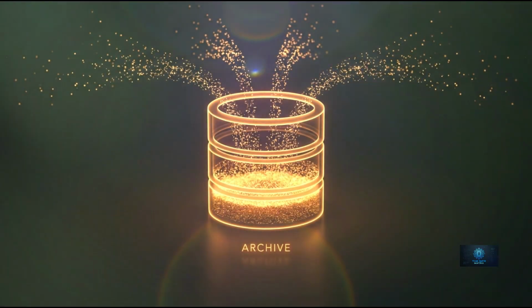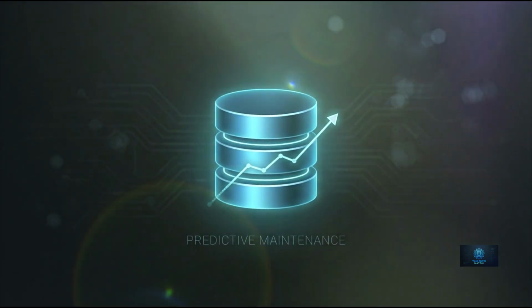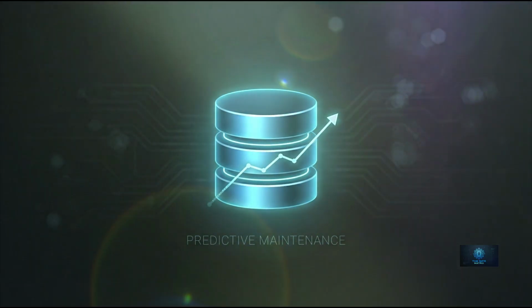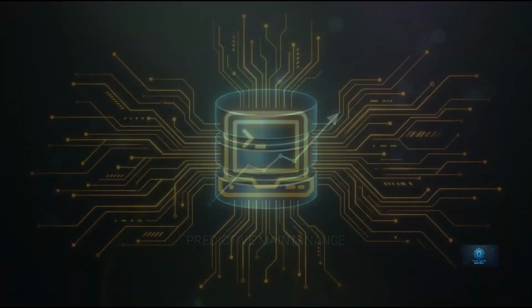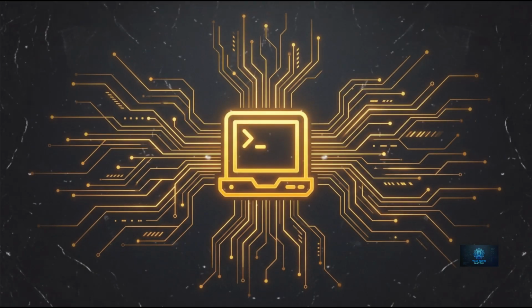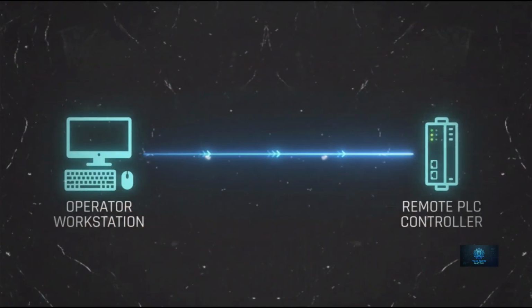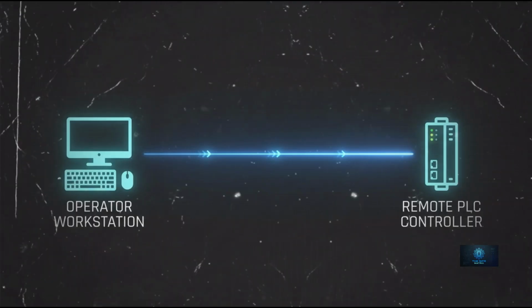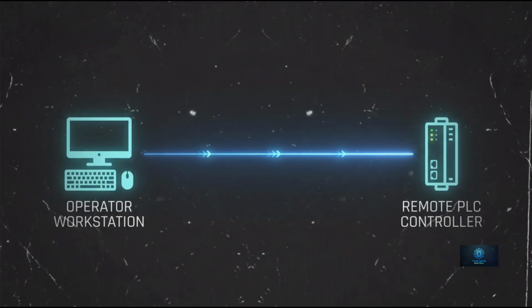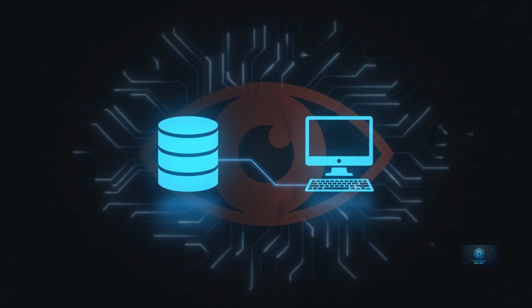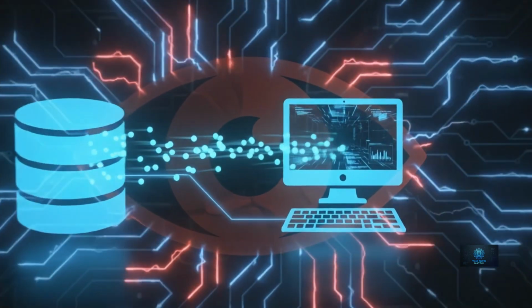Two more pieces round out a typical SCADA environment. The historian is essentially a specialized database, quietly logging every single reading, every alarm, every command, over months and years. It's what lets engineers spot slow-building problems, like a pump gradually wearing down, long before it fails. And the engineering workstation is where technical staff configure the system itself, writing the logic that tells a PLC exactly how to behave. Both are incredibly valuable to keep the plant running smoothly. And both are increasingly valuable to an attacker looking to understand a target in detail.